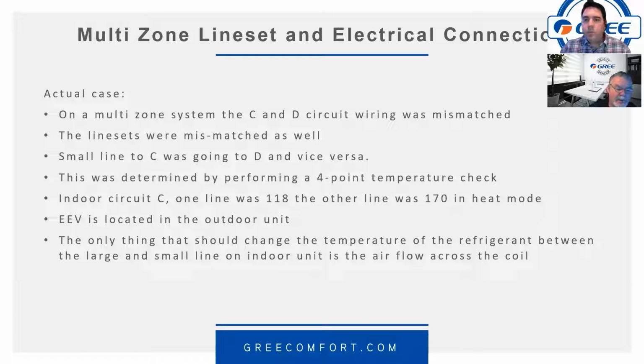Right. And so like these bullets say down here, the EEV is located in the outdoor unit. So when you're testing those pipes on the indoor unit, the only thing that should change the temperature of the refrigerant between those two lines is the airflow across the coil. Yes. And that's usually about 5 degrees difference between the two pipes. Now, I'll tell you a secret that we've learned on the Flex system. If you're familiar with the Flex, you've got service ports indoor and out, so you can hook your gauges up at both places, but there's not a true suction port. So your pressures at that point are going to be close to the same on those two pipes in heat mode, about 10 difference, and you know you're in a good spot. So that 5 degree difference and that 10 difference is a good rule of thumb to see if there's a restriction somewhere that you need to look for.